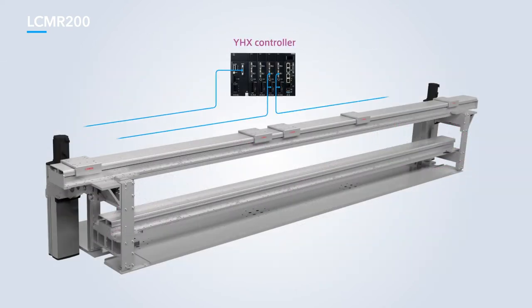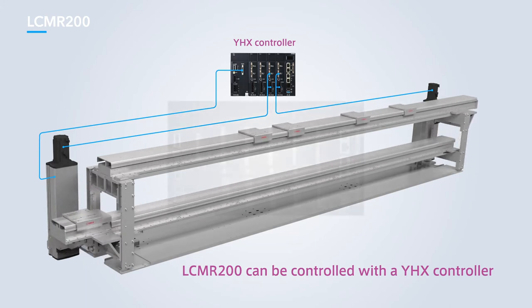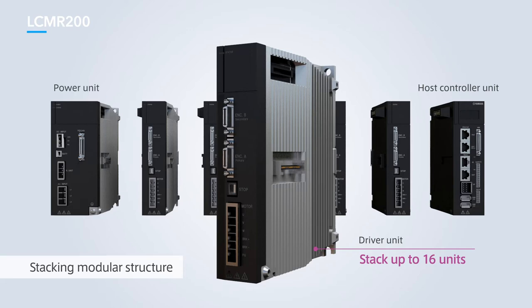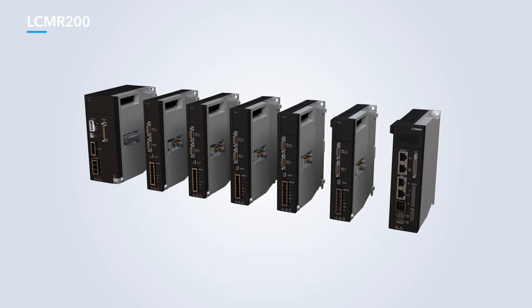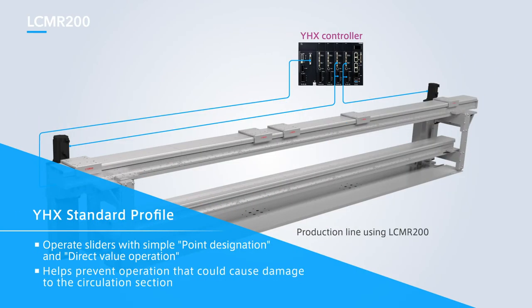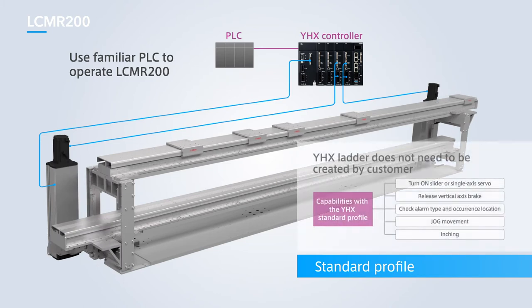Even with long production lines, LCMR200 can be controlled with a single YHX controller regardless of how many modules are installed. One of the main features of the YHX controller is its stacking modular structure, which comprises the host controller unit, driver unit, and driver power unit. The control power supply, motor drive power supply, high-speed network communications, and safety circuits all have a stacking modular structure, which reduces wiring immensely and eliminates wiring between units, leading to a significant reduction in wiring costs and man-hours. Lines are controlled by the YHX standard profile, which allows for simple and intuitive control even when operating multiple sliders, drastically reducing the man-hours needed to set up a line.